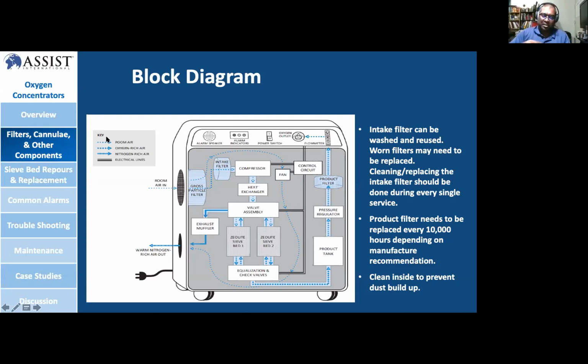When you give air on that particular line, the sensor converts it into millivolts and sends a signal to your display. The display measures the millivolts, but you do the conversion into percentage. So at 21%, the millivolt can be somewhere around 10 millivolt, and it measures up to 120. Normally they do calibration at 21 and 100 to make sure the ratio line is inside that range.